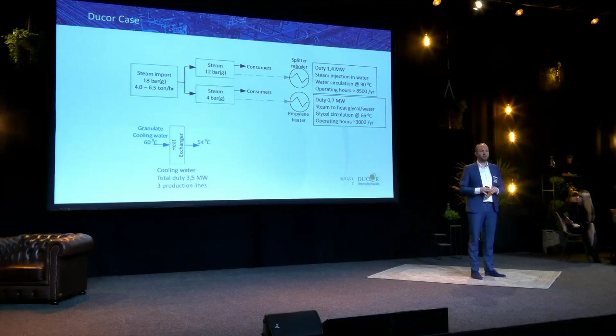On the other side, we have quite some excess heat in our extrusion section. The granulate is cooled down just after the die in the extruder with cooling water, which heats up from 54 to 60 degrees. That cooling water in circulation is again cooled down centrally in the plant. Every line has such a system, and the total duty is about 3.5 megawatts.